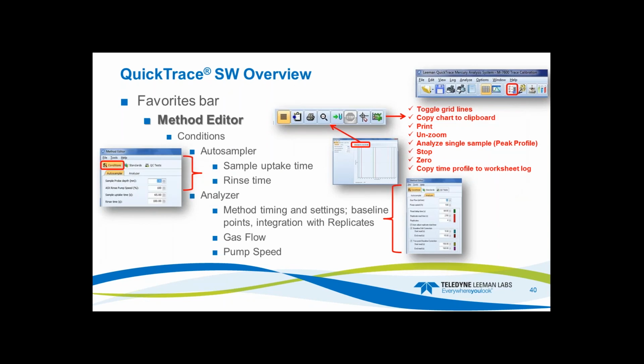Under conditions, so the autosampler, this is where you set up your uptake time for the sample and then your rinse time. And then under the analyzer tab, over here, that's where you have the timing for the method. So baseline points, integration, replicates, gas flow, pump speed, and all that. And then also above the graph on this UI, here's a blow up of the favorites bar for that, and you can toggle grid lines, copy the graph to clipboard, print, unzoom, analyze single sample, that's your peak profile, stop, zero, copy time profile to the log. So when the peak comes up, and if you click on this button, it will move that over to your log. So quality control always has a visual of what you saw when you developed that method or ran that analysis for that customer.